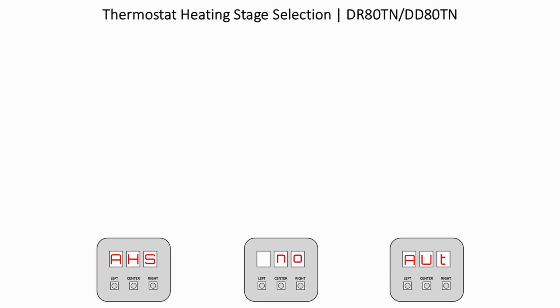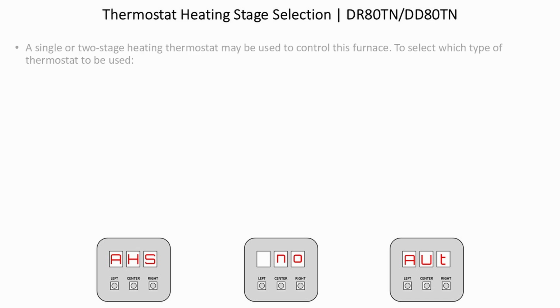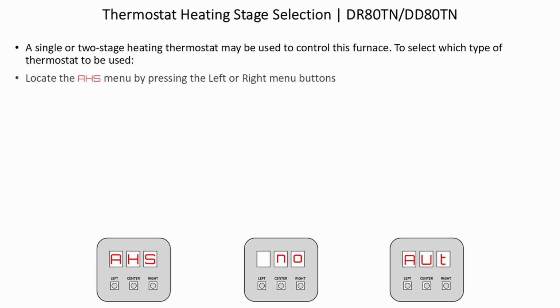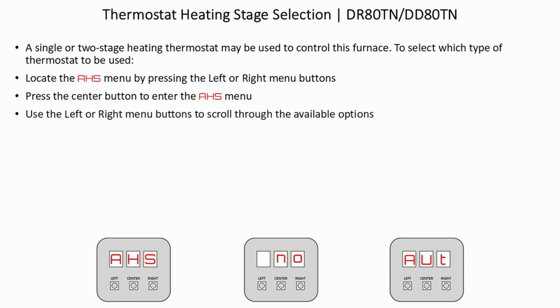Thermostat heating stage selection for the DR80TN and the DD80TN. A single or 2-stage heating thermostat can be used to control this furnace. To select which type of thermostat you are using, locate the AHS menu by pressing the left or right menu buttons. Press the center button to enter the AHS menu. Use the left or right buttons to scroll through the available options. NO is a setting for a 2-stage thermostat, which is the default setting.